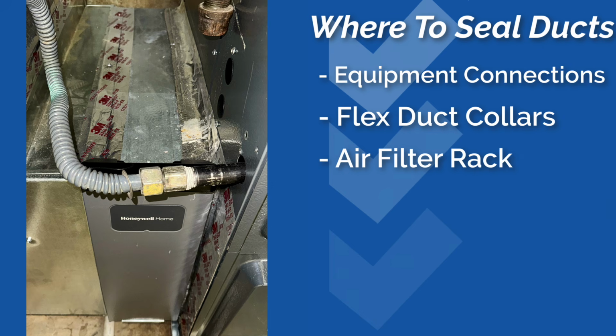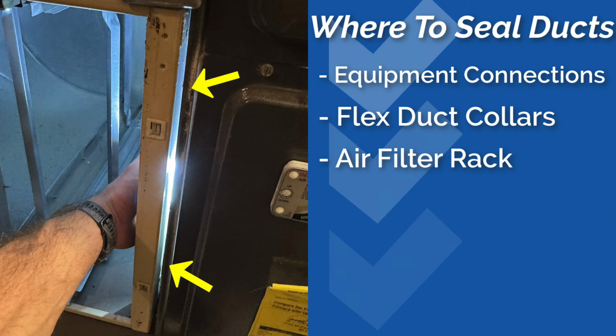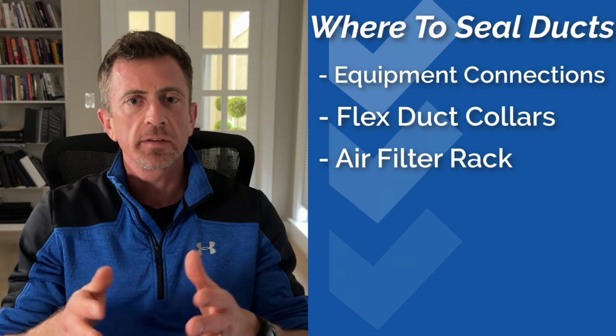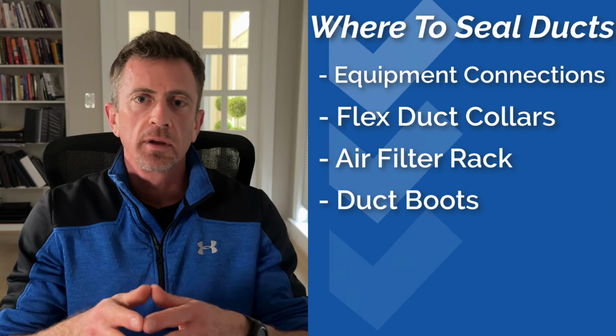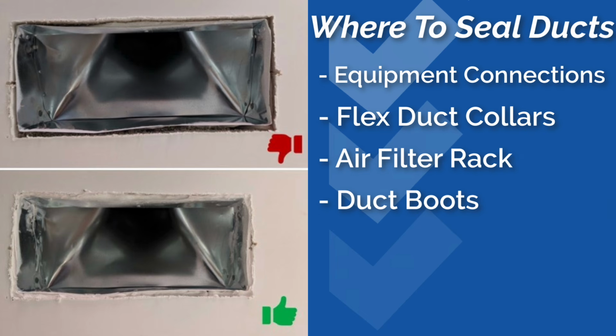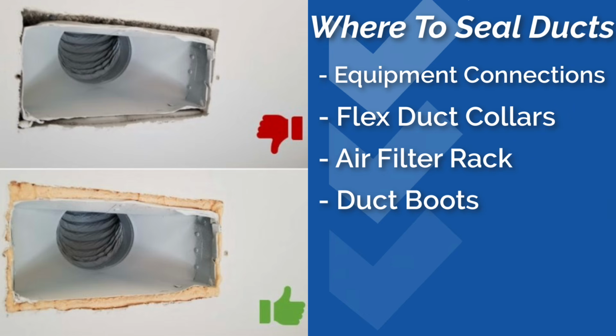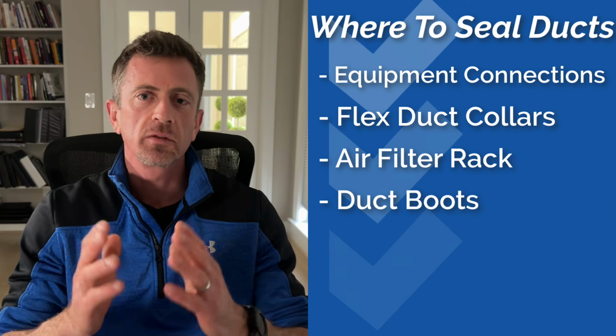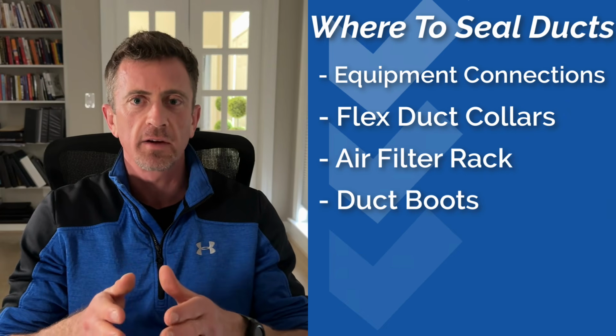The air filter rack itself is another big one. Seal all 4 sides, both the intake and the output side of the filter rack, to the duct system or to the equipment. If the output side isn't sealed, air can bypass the filter and get into the system. Another place to seal are the duct boots. Seal all the duct boots directly to the drywall or subfloor, not just to the grills or registers. This one is often missed in new construction, and when we do duct leakage testing for code compliance, this is one of the main things that can cause the house to fail.